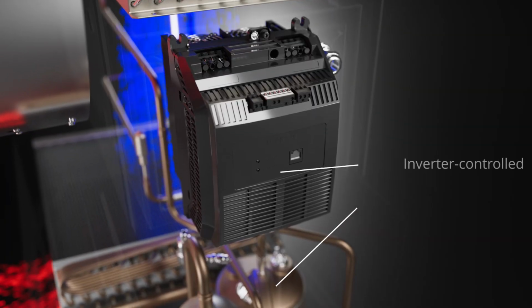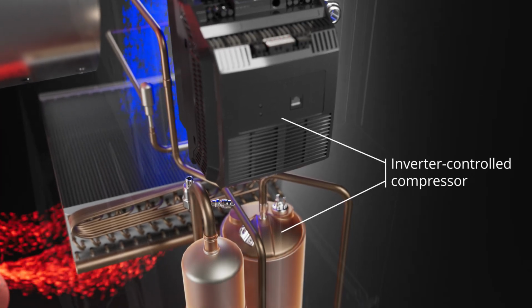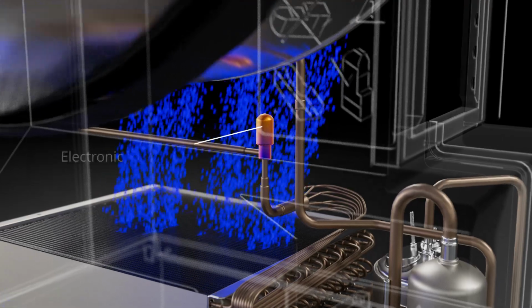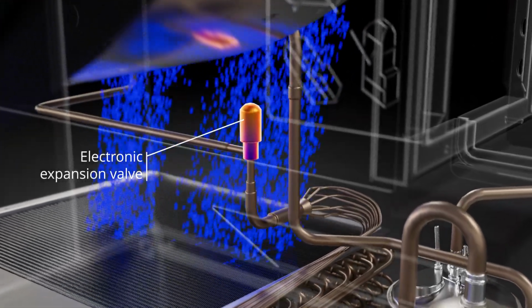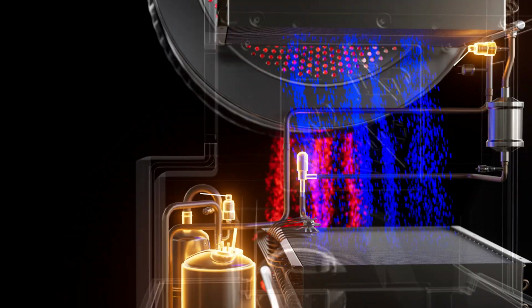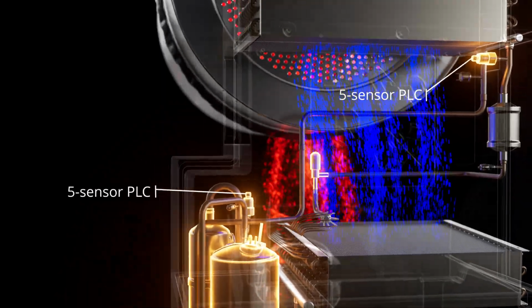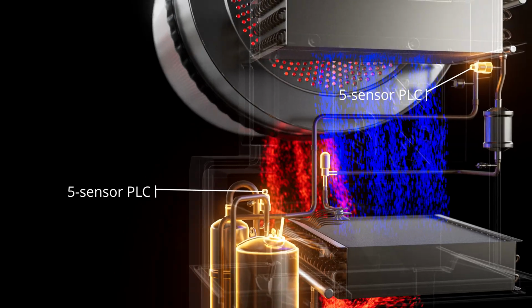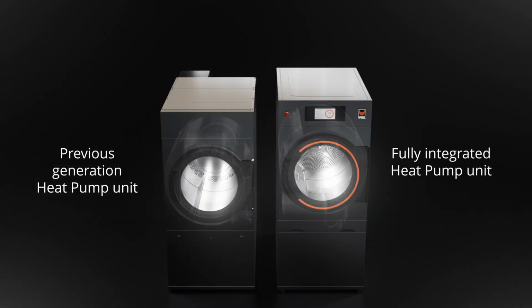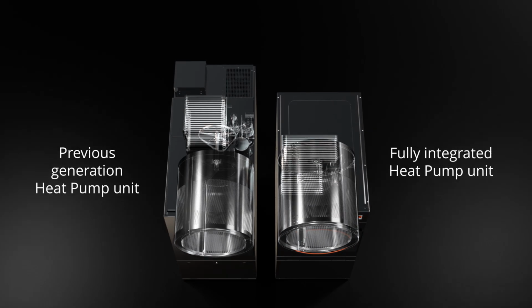This closed loop keeps running. There's no need to restart the heating process each time. An intelligent control system adjusts refrigerant flow, pressure, and heat exchanger temperatures, keeping the drying process stable from the first minute to the last.